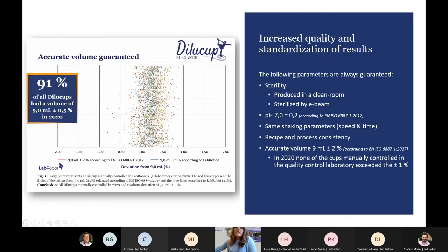With Dilucup, the results are standardized. The sterility of the diluent is always guaranteed since the Dilucup is produced in a clean room and sterilized by e-beam. The pH is always in the interval of 7 ± 0.2 according to ISO 6887, but in practice it is actually within 7 ± 0.05, always. The recipe of the diluent and the shaking parameters — speed and time — are always the same.